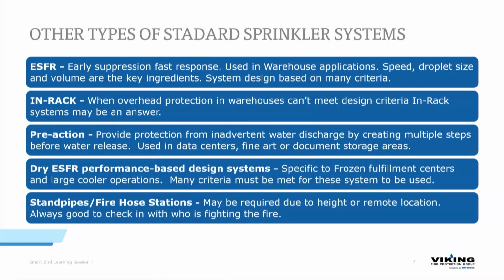Pre-action systems. These are going to provide you a level of redundant protection if you're protecting something like document storage areas, even data centers, fine art. So your pipes are going to be empty until you get one signal. And that signal could be a UV detector, a smoke detector, some other type of detection that is going to tell you you might have an issue in this room. And when that happens, water would come into the pipes, but nothing is going to happen until that sprinkler head goes off. There's different levels of redundancy you can set up in a pre-action system.